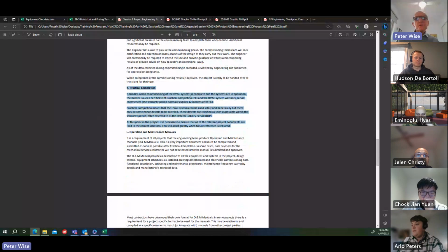Normally when commissioning of the HVAC systems is complete and the systems are in operation, the builder will issue a certificate of practical completion, and the HVAC system warranty period will commence. The warranty period is normally 12 months after practical completion. This means the HVAC systems can be used safely and beneficially by the client, but there may be some minor defects to be rectified. So it's running satisfactorily, but there might be a few things we need to finalise or fix up. These defects are rectified as soon as possible within the warranty period, which is also called the defects liability period - during that 12 months, all these defects need to be rectified as soon as possible.